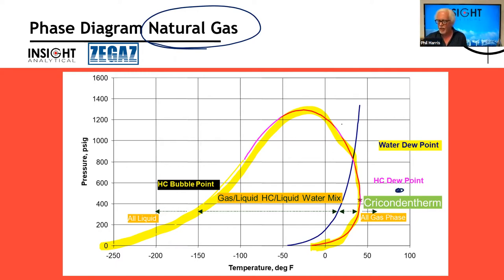at some elevated temperature, it says it's all going to be gas on this side. As we cool the stream down and it crosses this phase envelope, that says, well, that's the first place that liquids are going to come out. And those liquids in this case will be hydrocarbons. So this would be our hydrocarbon dew point. So as we cool that gas down, we touch that phase envelope. Just like dew forming on the grass, as it cools, all of a sudden liquids show up there.